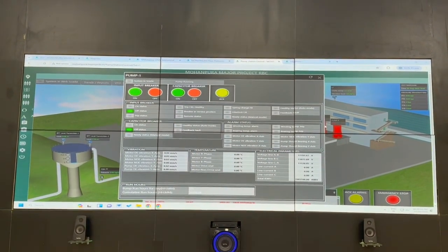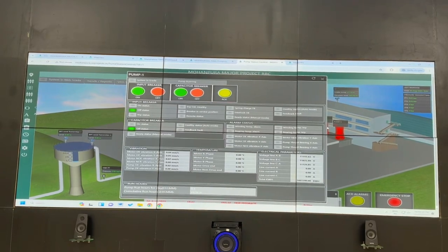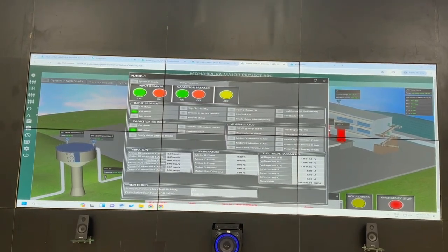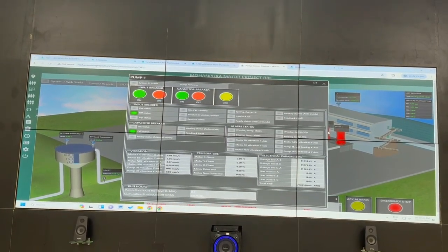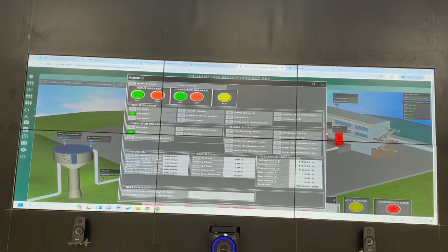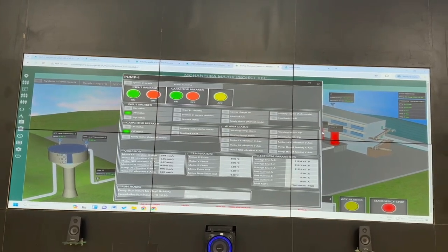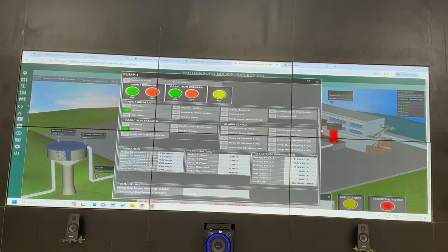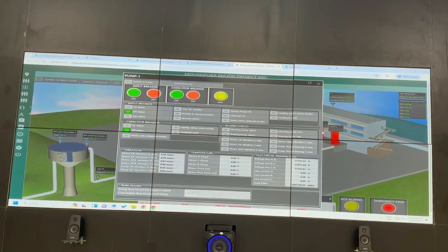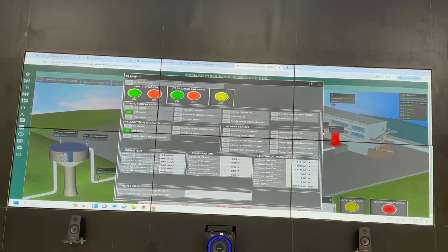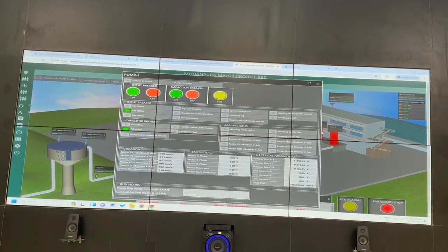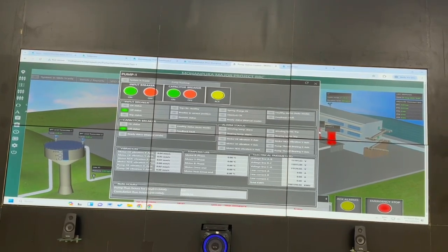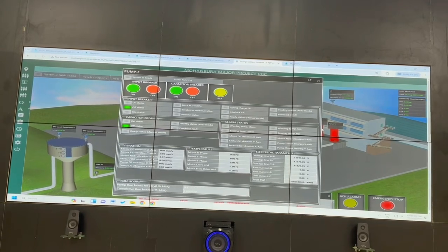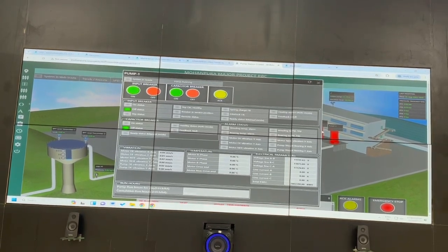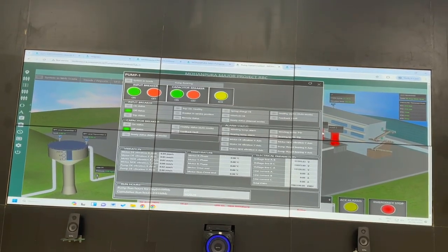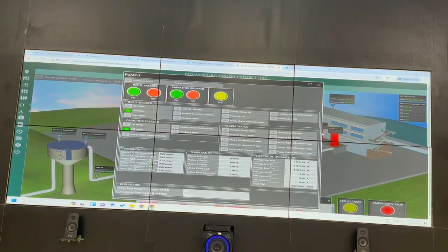Now this is the pump vibration status. You can see the driving, non-driving, vibration, temperature, all the critical parameters are being monitored. Every parameter has a set limit. If any limit is violated, then there will be an alarm. There are two types of set limits. When it crosses the first threshold, an alarm is generated. If it crosses the upper limit, it is auto cut, or a shutdown of the whole system happens.